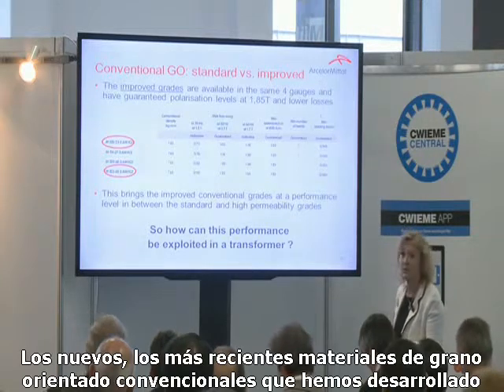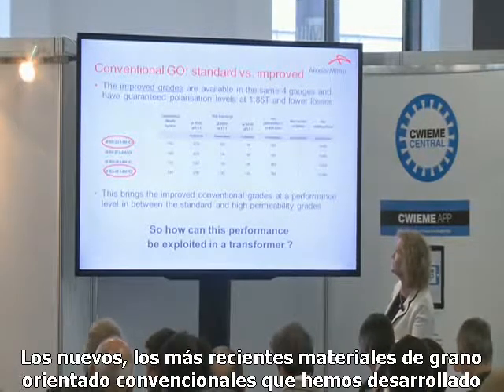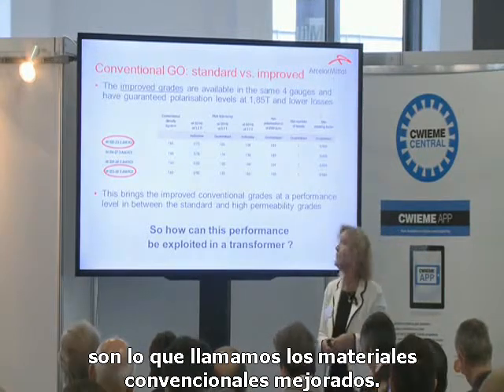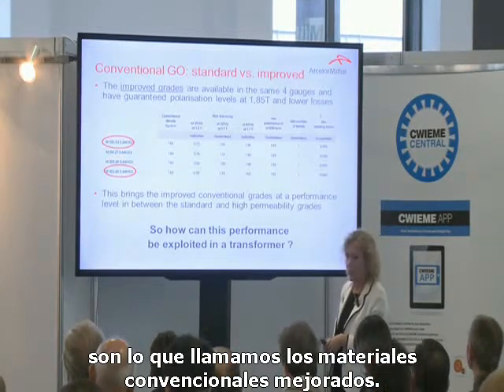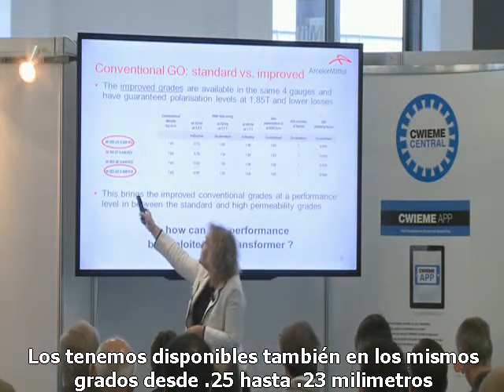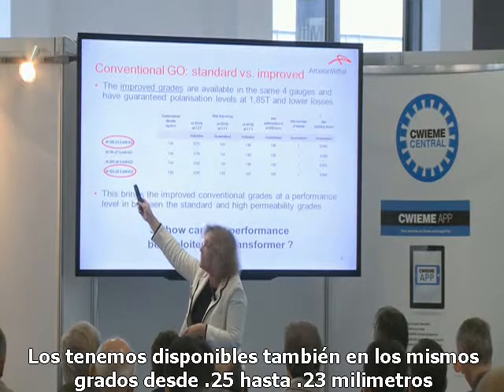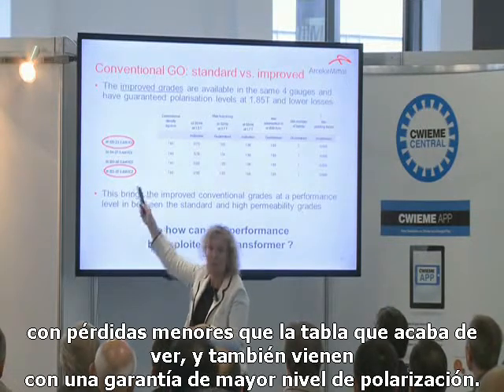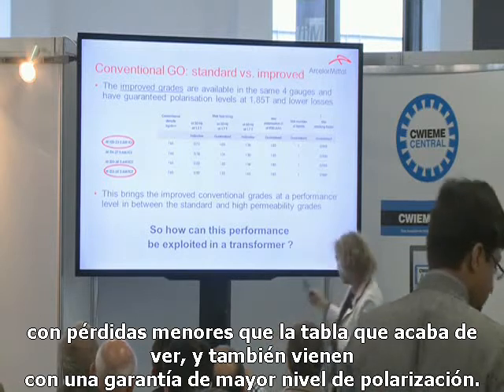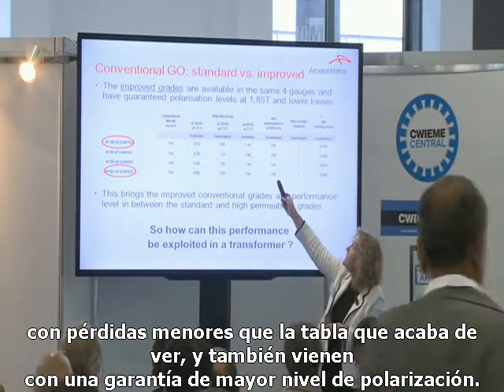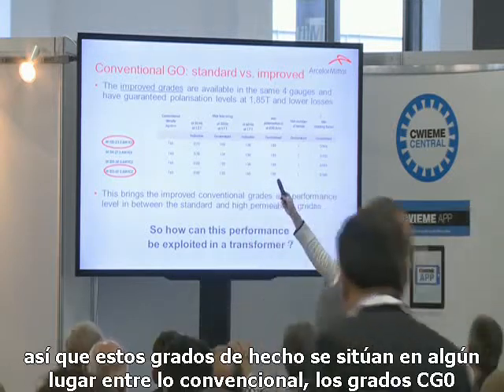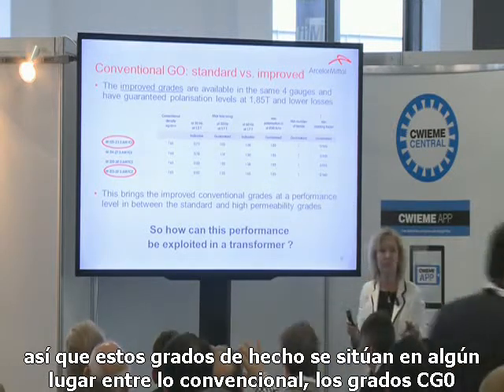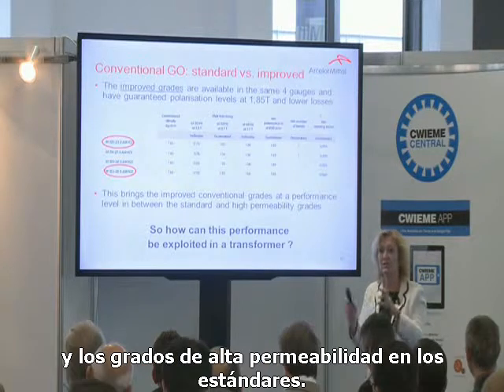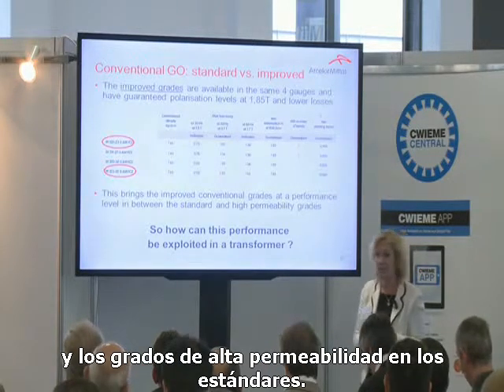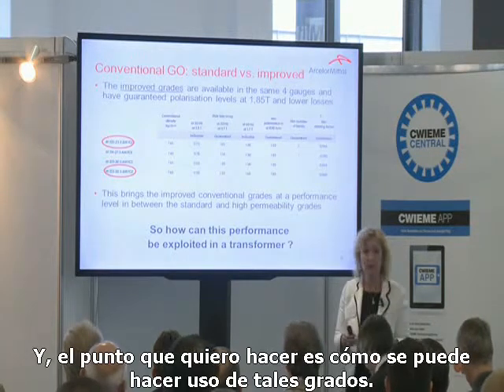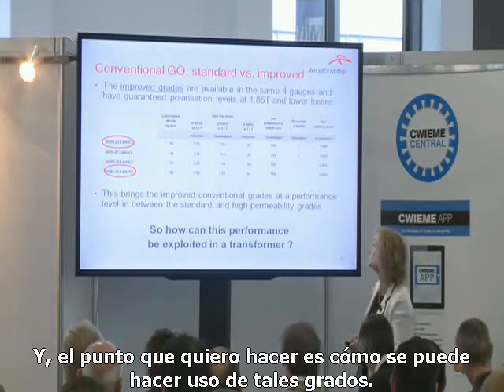The newer conventional grain-oriented materials we've developed are what we call improved conventional materials. They're available in the same gauges, 0.35 to 0.23 millimeter, and come with lower losses than the table you just saw, as well as a higher guaranteed polarization level. These grades sit somewhere between the conventional CGO grades and the high permeability grades in the standards. The point I want to show is how you can make use of such grades.